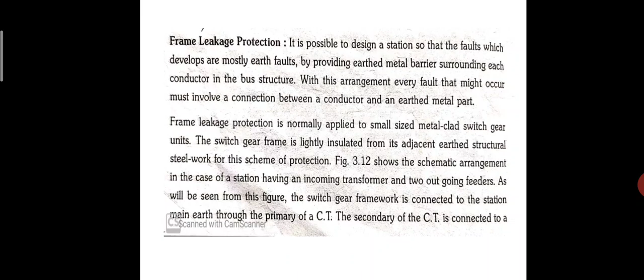The switchgear frame is lightly insulated from its adjacent earthed structural steelwork. For this scheme of protection, the arrangement in this case is a station having an incoming transformer and two outgoing feeders, as will be seen from this figure. The switchgear framework is connected to the station main earth through the primary of the CT. The secondary of the CTs is connected to a sensitive frame leakage relay. In the event of earth fault currents flowing in the switchgear framework, this relay will operate.